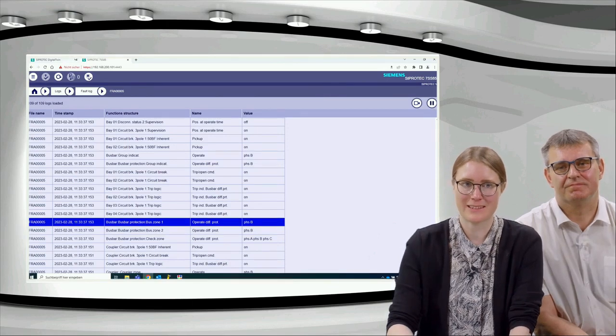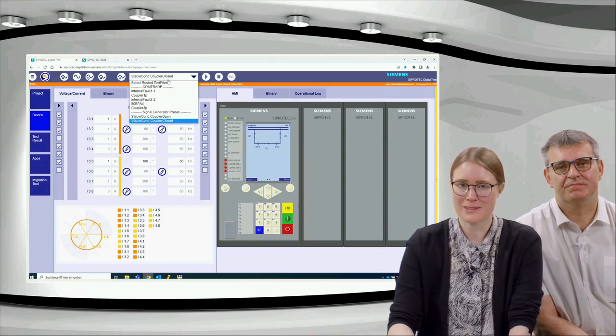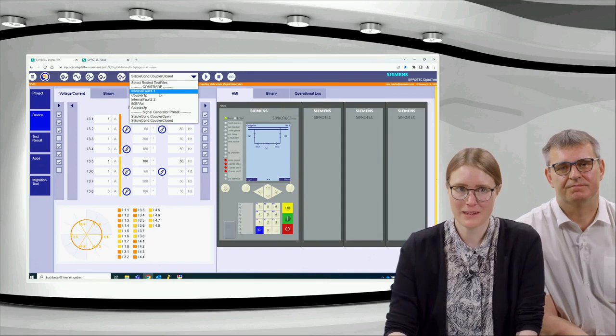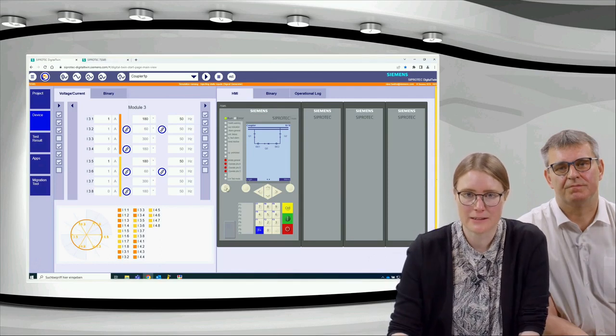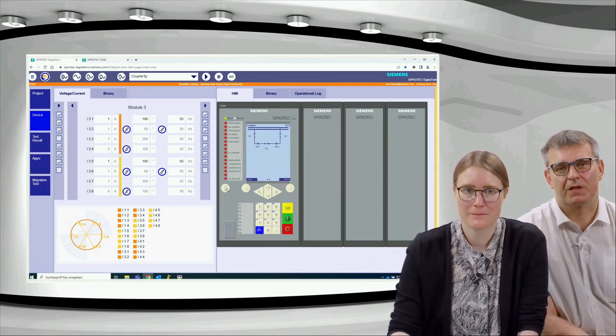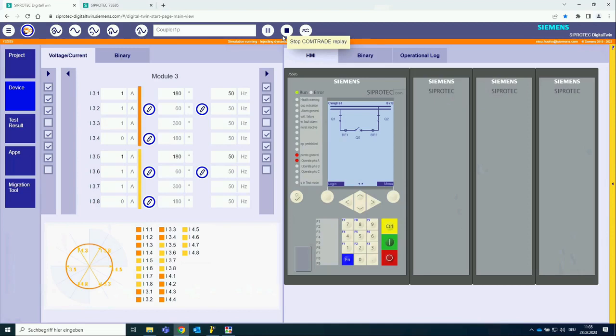And let's demonstrate the second scenario. The coupler closed scenario is already active. And now I jump to the coupler fault 1-pole and replay this one. Maybe I clear the LEDs. And now we're expecting really a so-called sequential tripping, or first only tripping the coupler, applying the end fault, and then only the faulty zone should be cleared. Exactly.